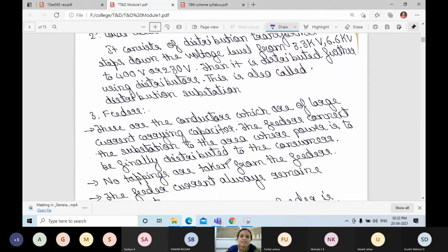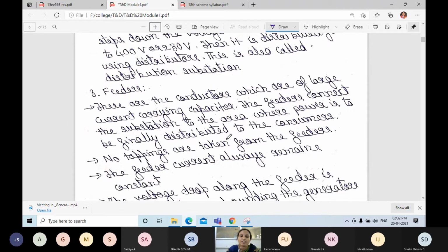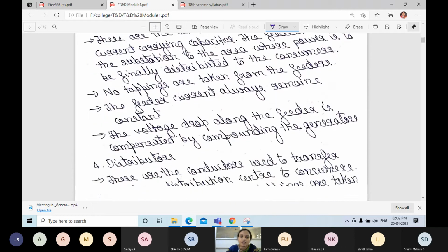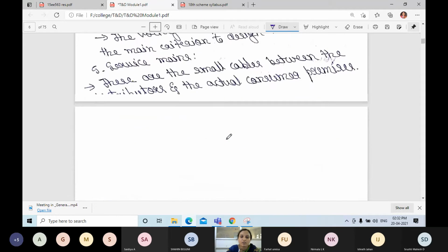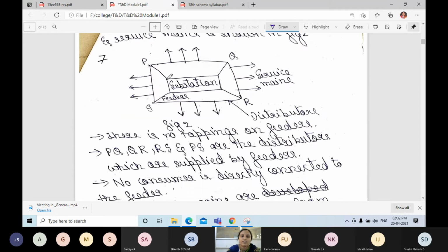Next. These are the conductors which have large current carrying capacity. The feeders connect the substation to the area where power is to be finally distributed to the consumer. No tappings are taken from the feeders. The feeder current always remains constant. Here you will observe the diagram also. From that you will understand. This is a substation. Okay. From the station, P, Q, R, S, these are the feeders. Okay, there are no tappings on feeders.